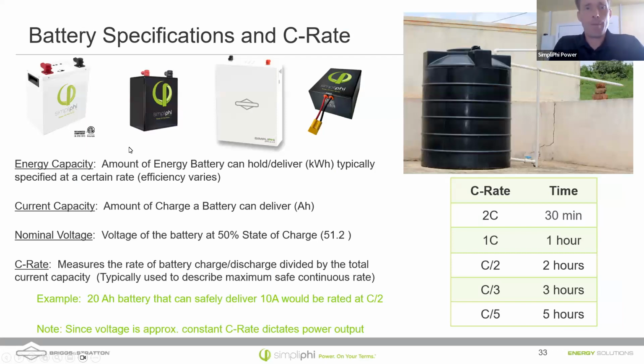So let's talk a little bit about the specifications of batteries. There's the energy capacity of batteries. It's the amount of energy that a battery can hold, typically measured in kilowatt hours, and it's often specified at a certain rate. So you get the most energy out of a battery if you discharge very slowly. The faster you discharge, the more heat you produce. This is known as the Peukert effect. But basically, it's simply understood in terms of Ohm's law, right? Ohm's law says that the amount of heat generated is I squared R, the square of the current. And so the slower you do it, the lower the current, and the less heat you generate.